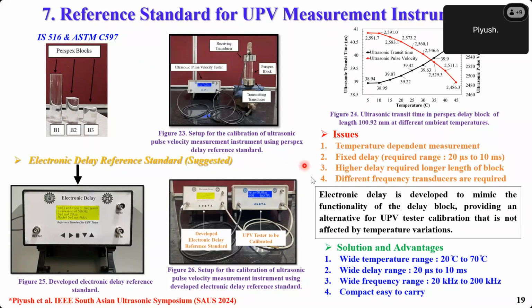To mitigate these issues, I have developed an instrument, an electronic delay, which mimics the property of this calibration block and is not affected by temperature variation. These are the advantages of using this electronic delay reference standard. It can work from 20 degrees Celsius to 70 degrees Celsius, and it has a wide range of delay from 20 microseconds to 10 milliseconds. It also has a wide frequency range, so we do not need different frequency transducers to calibrate with this instrument. Here you can see that it is very compact and easy to carry. So this is a good product for the industry also.